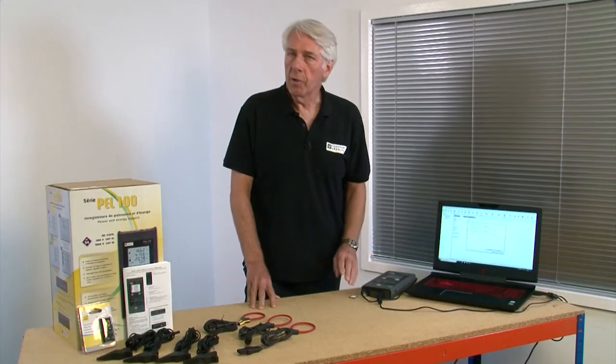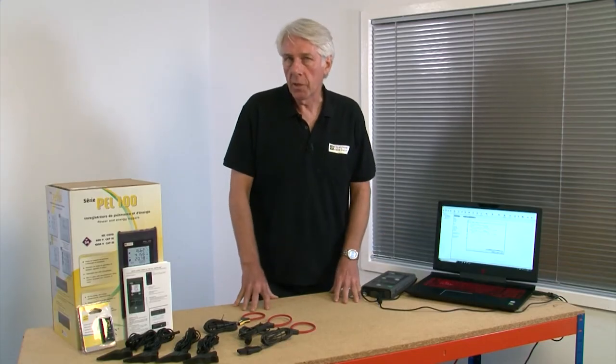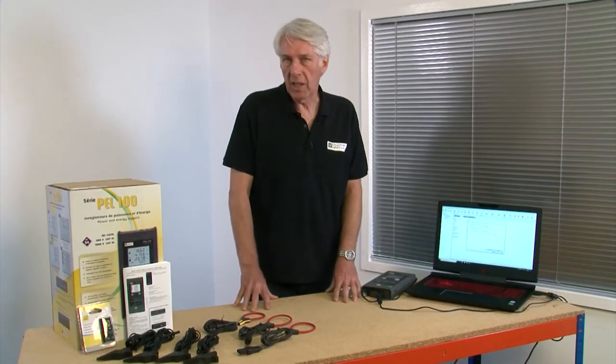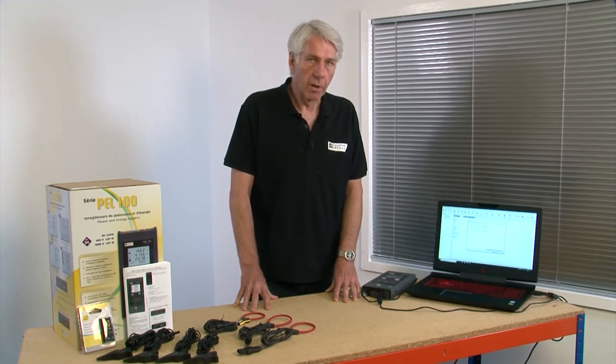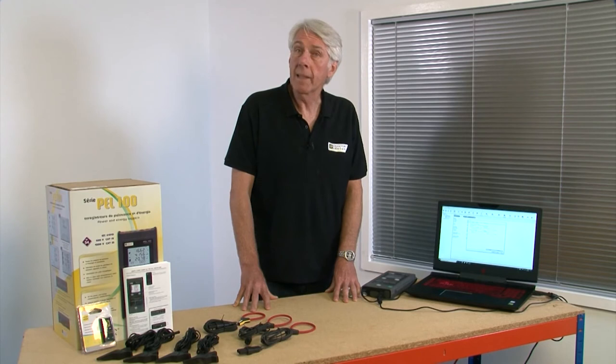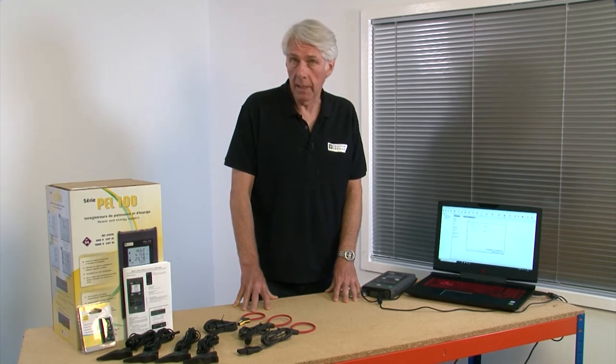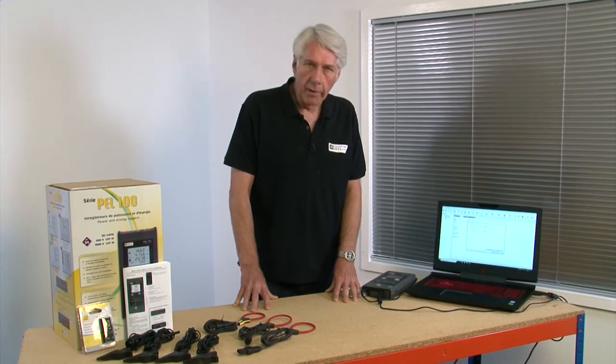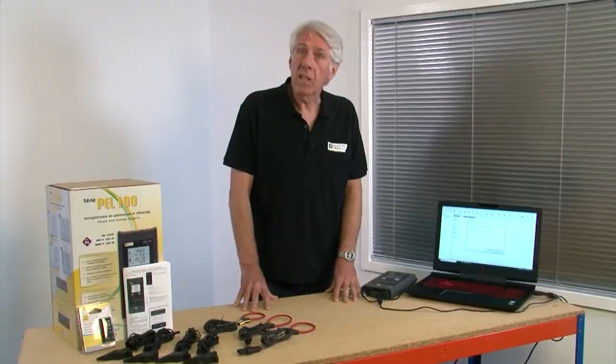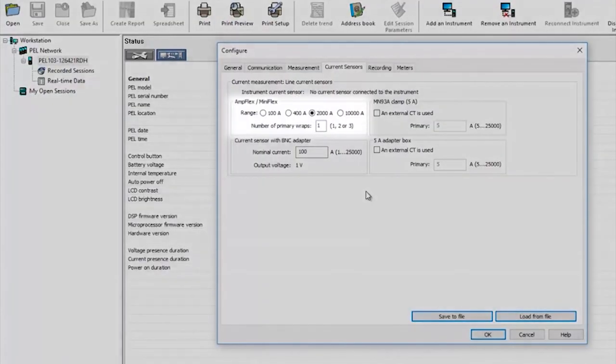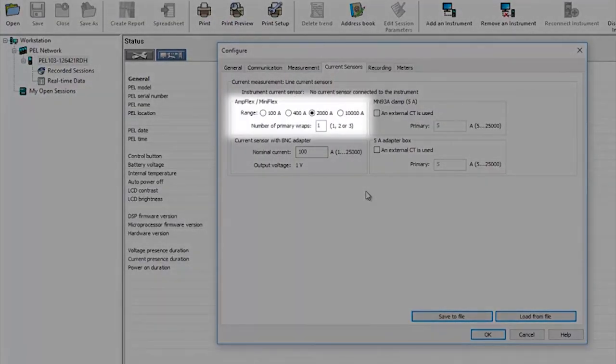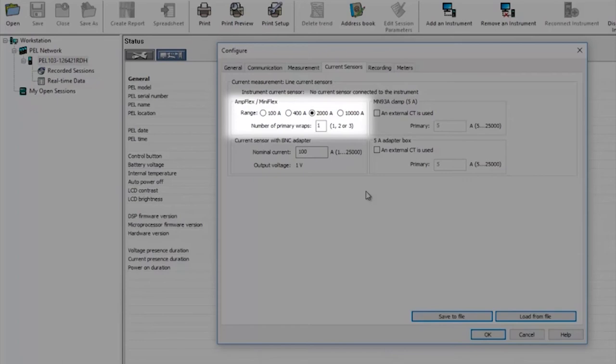For the majority of situations where you're putting flexi clamps directly around the installation cables you will not need to set any ratios and the PEL will automatically detect the current clamps you've plugged in. You should however select the expected maximum current for the installation here and this will ensure the readings taken are the best resolution available. So if you have an installation that's likely to have a thousand amps flowing at any time you'd select the 2000 amp setting. For 200 amps you'd select 400 amps and so on.